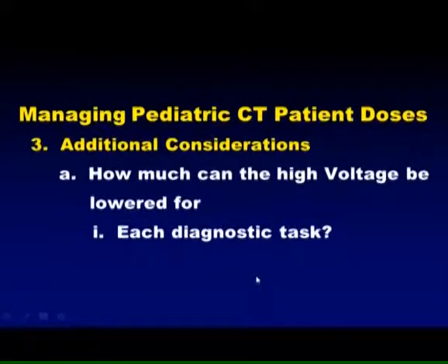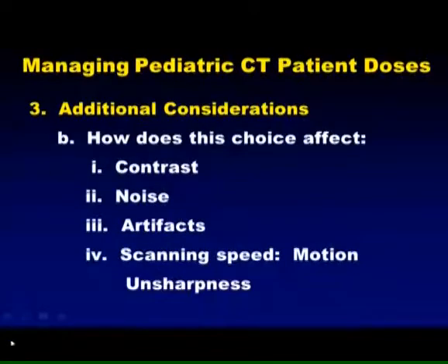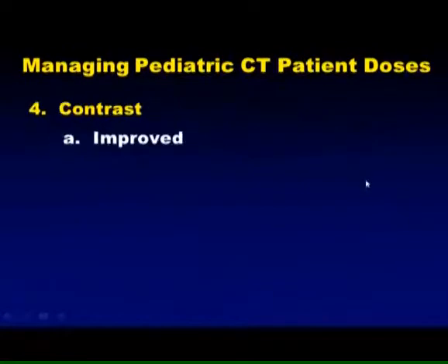So, some additional considerations. How much can the high voltage be lowered? Well, it depends on the task. It depends on the patient size. And of course, as I lower the kV, I'm going to change the contrast, the noise, the artifacts, and the scanning speed. So let's look at that a little bit.